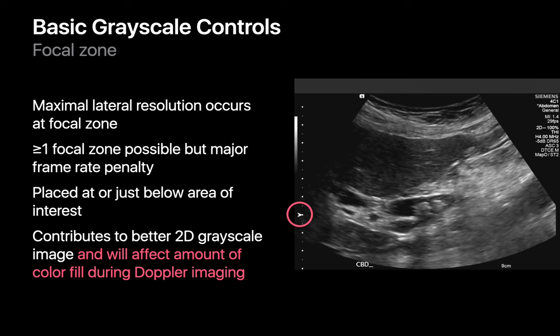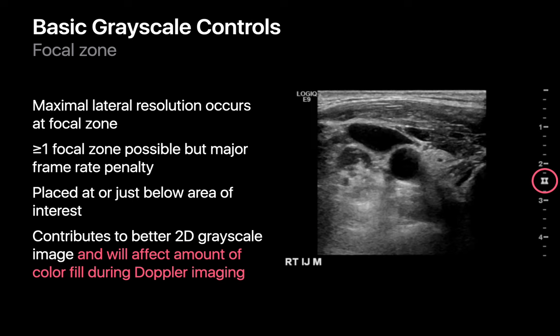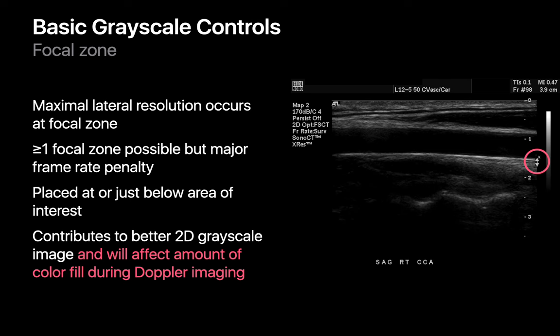Focal zones are a specific depth within an ultrasound image where the ultrasound waves are most tightly focused and where lateral spatial resolution will be the best. The focal zone location is indicated by an arrow along the depth markings on the side of the image. It's possible to set more than one focal zone, but this comes at a major frame rate penalty. The focal zone should be situated right at or just below the object of interest, as good placement also affects how good your Doppler imaging will be.